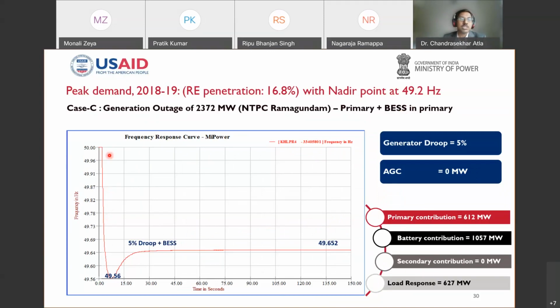You can see here, even though the inertial response and falling of frequency is not much improved, your frequency does not go down to 49.2 — it is arrested at 49.56. This is where batteries started deploying their response into the primary reserves and the inertial response, because as you know, the battery is mostly a power electronics device with gate pulsing. It happens in a fraction of seconds, and hence the battery participates in the primary reserve, as reported in international studies also. So instead of going to 49.2, you are better placed because you have improved the frequency stability a lot. Then 49.56 got arrested, and my overall settled frequency is 49.65. Still, I do not have secondary contribution.